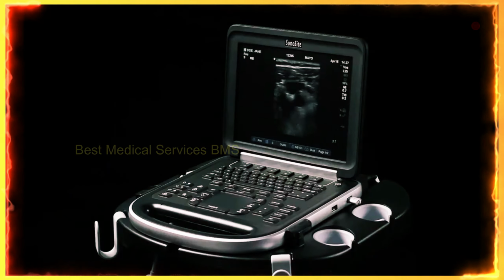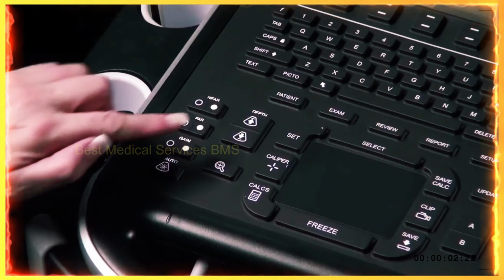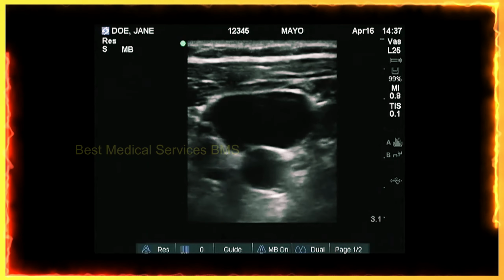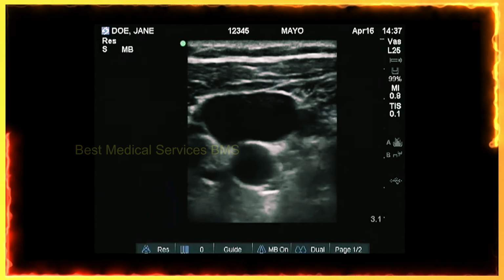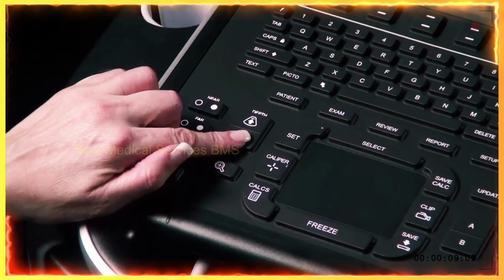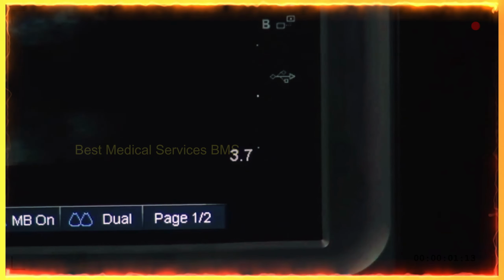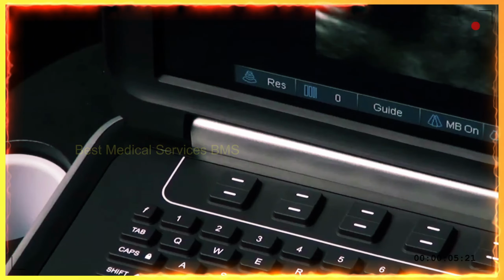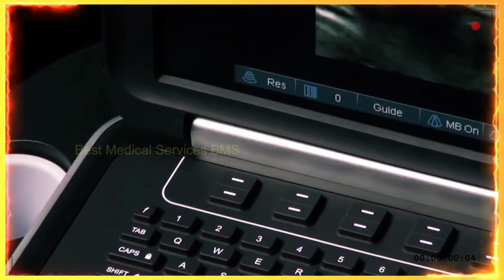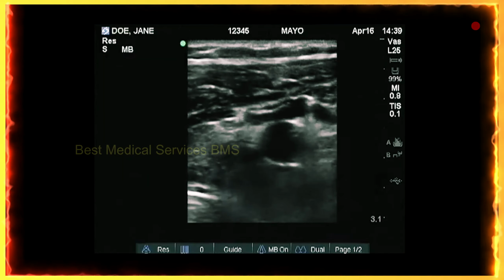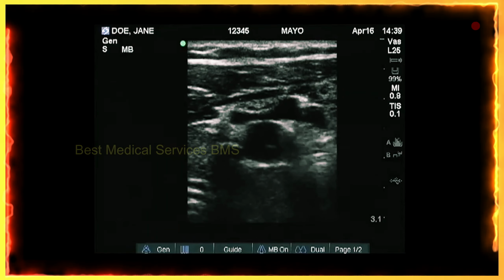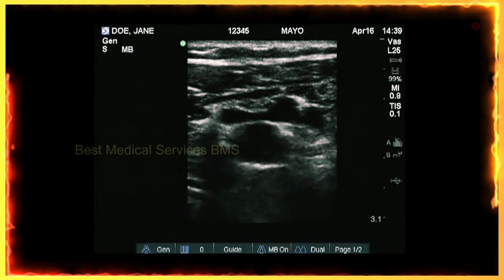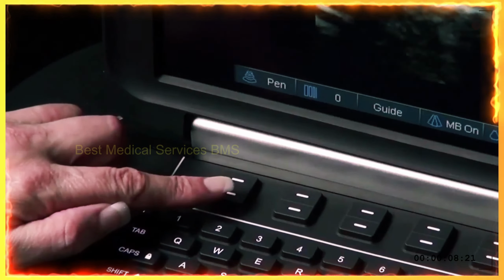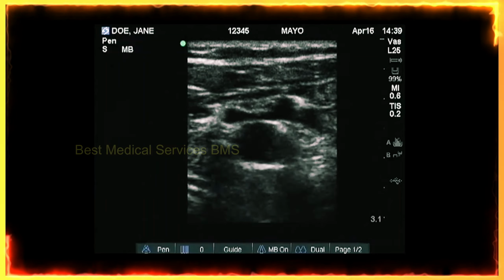Once you have located the area of interest, adjust the depth of image to center the area of interest in the middle of the image display. As you adjust the depth, the maximum depth number changes in the lower right corner of the screen. Select the desired optimization setting from the on-screen menu. Res provides the best resolution possible. Gen provides a balance between resolution and penetration. Pen provides the best possible penetration.